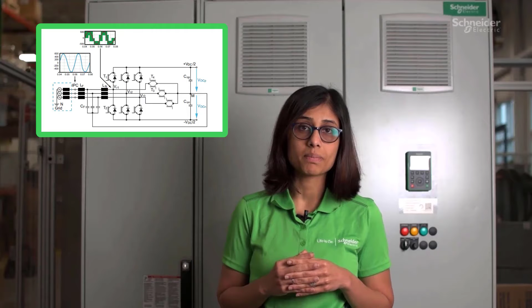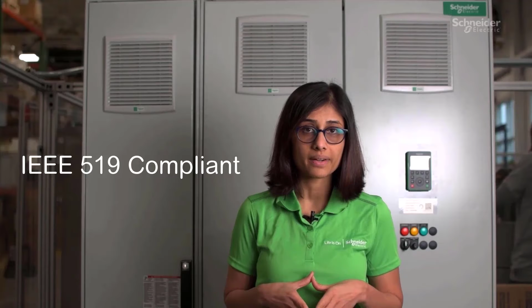Because of all these advanced features, we are able to achieve THDI of 2 to 3% on the input end of the drive, making this drive IEEE 519 compliant. When you compare this drive with other harmonic mitigation solutions which are used with diode front-end drives such as harmonic filters or multi-phase transformers like 12 pulse or 18 pulse transformers, these drives have smaller footprint, they are generally more efficient and they work better under imbalanced conditions.